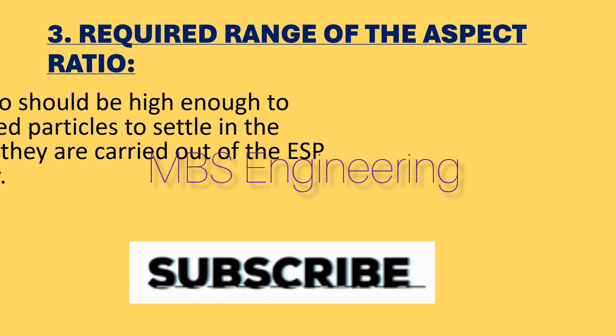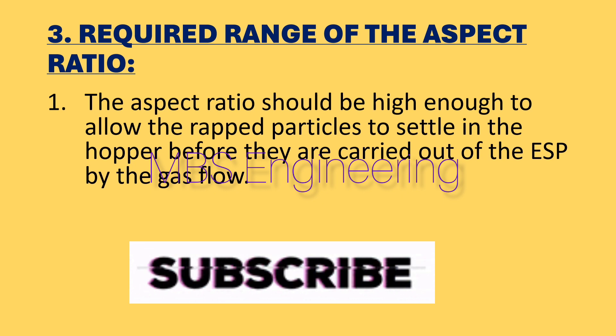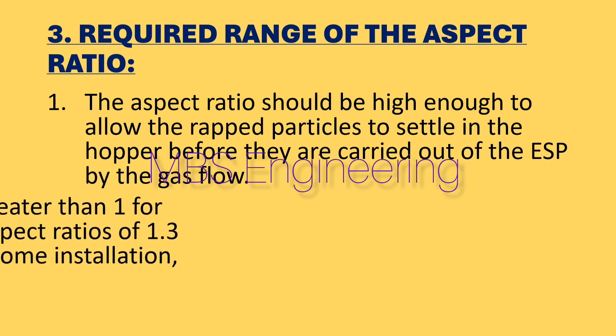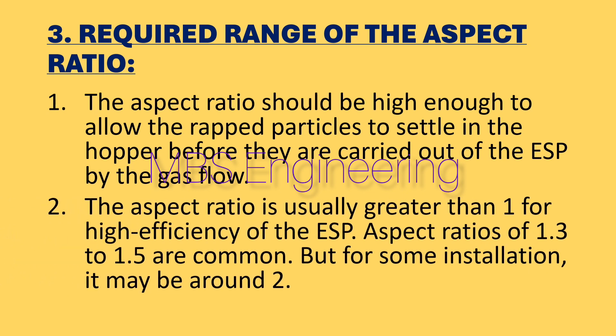Next, we are going to understand the required range of the aspect ratio in the ESP. Point 1: The aspect ratio should be high enough to allow the rapped particles to settle in the hopper before they are carried out of the ESP by the gas flow. Point 2: The aspect ratio is usually greater than 1 for high efficiency ESPs. Aspect ratios of 1.3 to 1.5 are common, but in some installations it may be around 2.